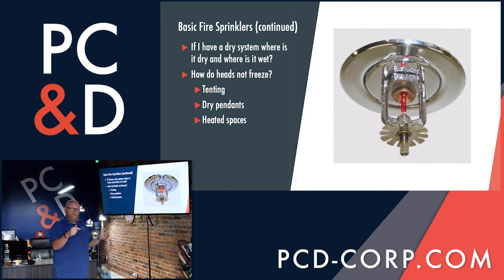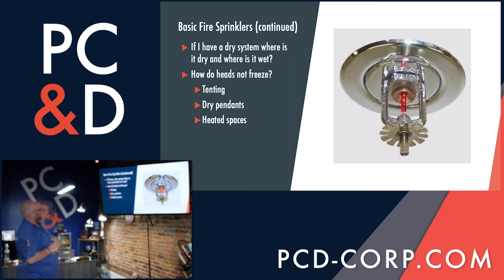Your next head is designed to be located so many feet away from it so that if it were to trip, its casting and spray will overlap each other so that you're able to put a fire out no matter where it is in your building. So that's kind of a quick little summary of a sprinkler head.